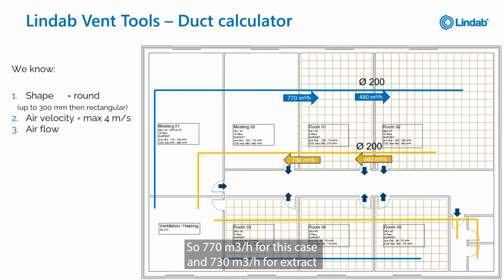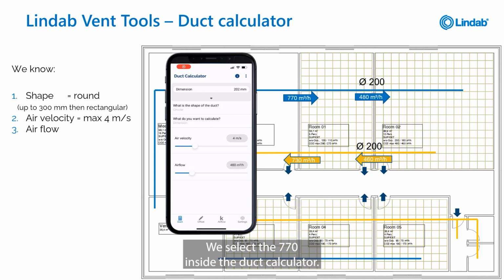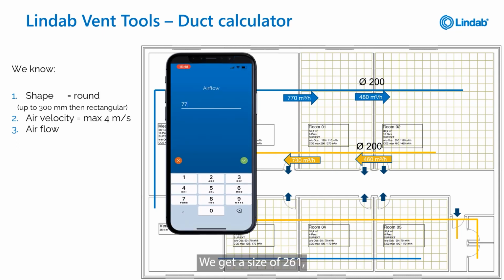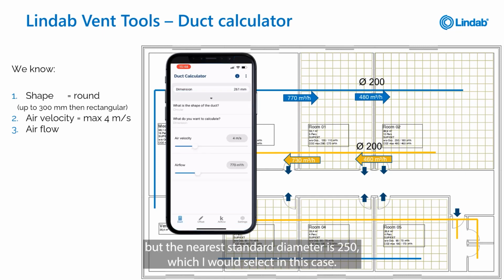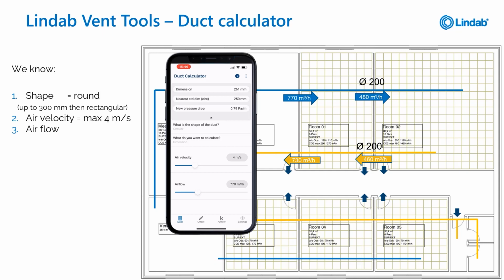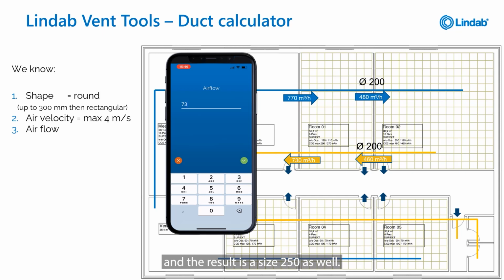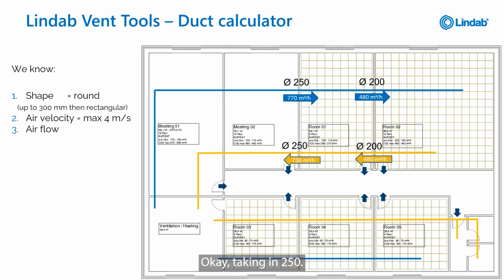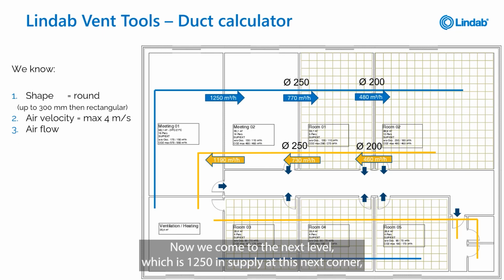If you take the next level, so 770 in this case and 730 in extract, we can do absolutely the same. We select the 770 inside the duct calculator. We get a size of 261, but the nearest standard diameter is 250, which I would select in this case. The same for extract. We take in 730, and the result is a size of 250 as well. Okay, taking in 250.